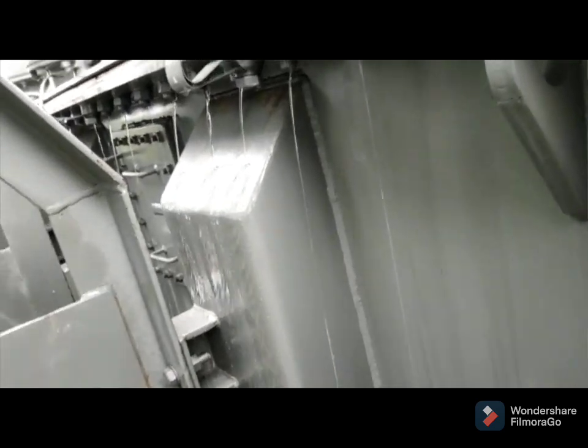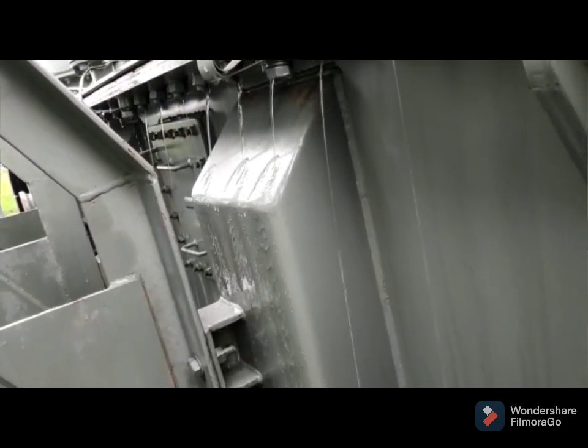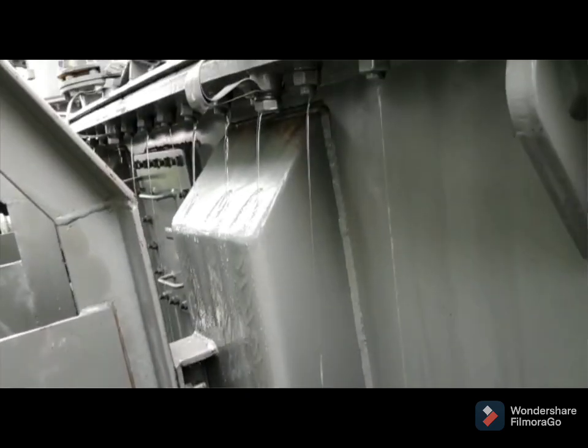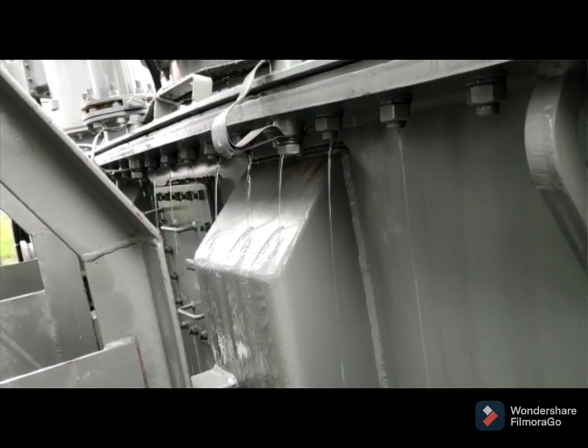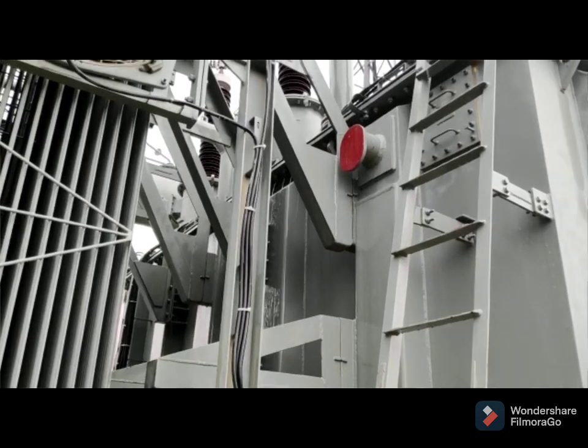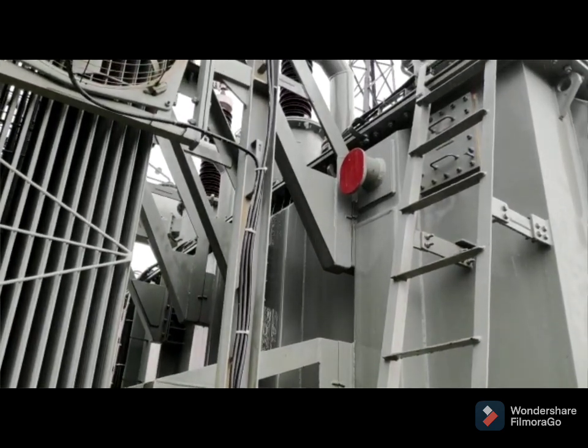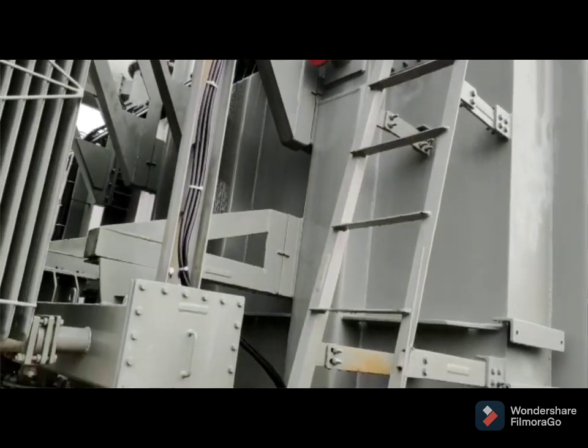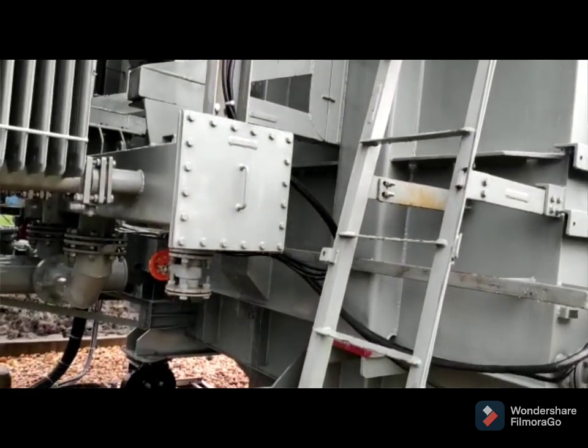The bending positions — I am showing the top plate of the transformer has been bent and all the nuts have shifted from their positions. The jacking pad and supporting bolts are also shifted. These are the inspection chambers — in between you can see from the ladders the inspection chambers, one from the bushing inspection chamber. All three bushings have different chambers.